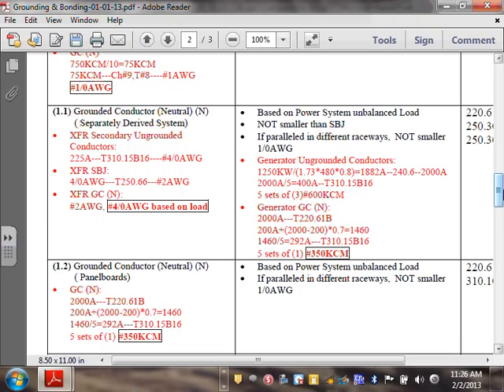If it's not a separately derived system, or if it's not service, because with a separately derived system and service, you have the main bonding jumper and the system bonding jumper to play with. But if it was just a subpanel, like a 2000 amp subpanel, how do you size a neutral for a 2000 amp subpanel? You don't have a main bonding jumper there, right? To worry about, or system bonding jumper.